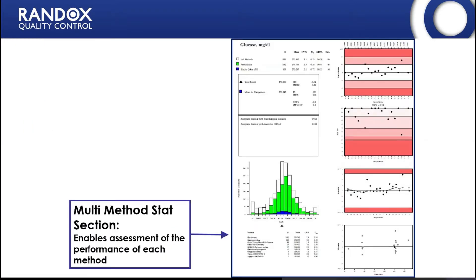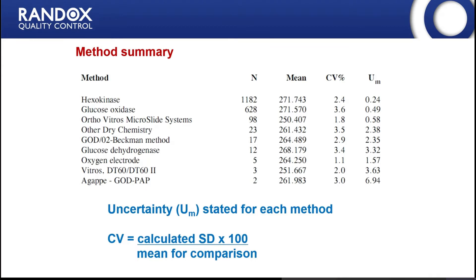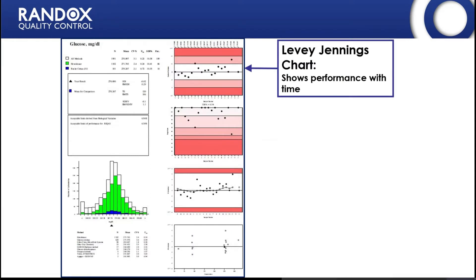At the bottom of the report we have the multi-method statistics section, which enables an assessment of the performance of each method used for this particular test. Any method with a peer group of at least two results will appear in this table. You can see the mean, CV, and uncertainty for each method. The CV is the standard deviation divided by the mean for comparison, multiplied by 100.